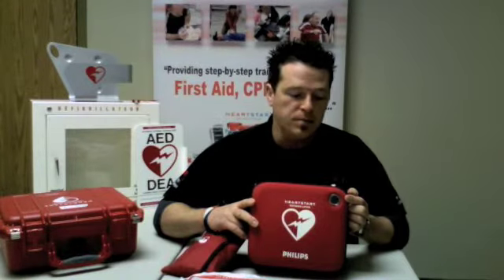last test. The defibrillator does a test on itself every day, every week, every month to make sure that the defibrillator as well as the battery are in working order, and it also makes sure that the gel consistency on the electrode pads is ready to be used as well. If it's not flickering green, that may mean that the defibrillator itself is not functioning. And maybe the main reason for you to do this servicing is because the defibrillator is chirping. The defibrillator will not have a flickering green light, will be chirping, and that means that something needs to be done in terms of servicing.